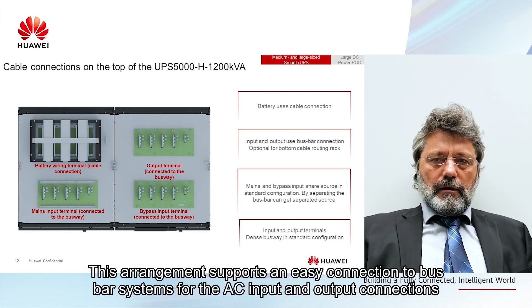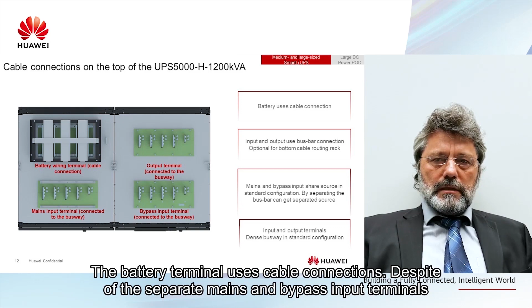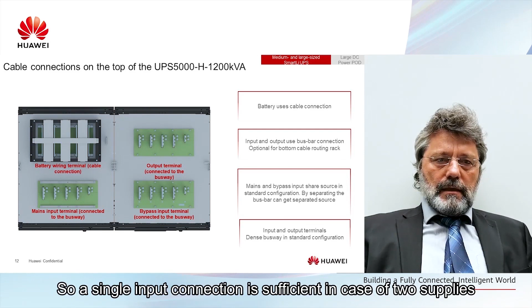In the standard, all power connections of the 5000H 1200 kVA are located on the top of the cabinet. This arrangement supports an easy connection to busbar systems for the AC input and output connections. The battery terminal uses cable connections. Despite the separate mains and bypass input terminals, the standard has an internal busbar link between the two sources, so a single input connection is sufficient. In case of two supplies, this link can be removed easily.